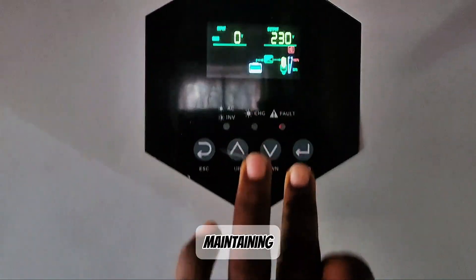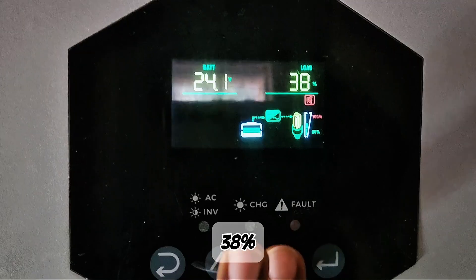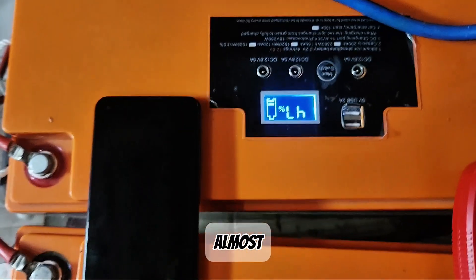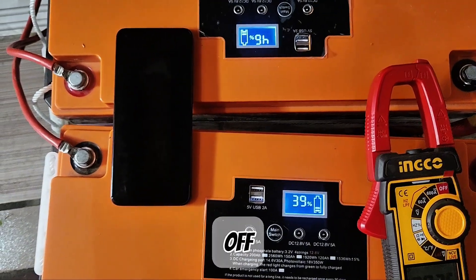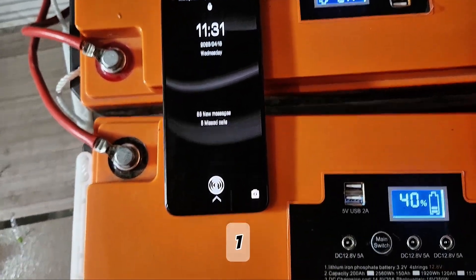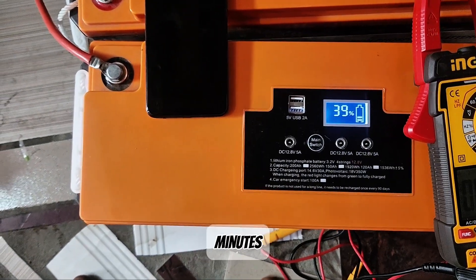Let's confirm the load — still the same 38%, 1,150 watts on both batteries. After one hour we've lost almost 50% from one and about 40-something percent from the other. After 61 minutes, the battery percentages are 39% and 40%. It should go off within the next 20 to 30 minutes.